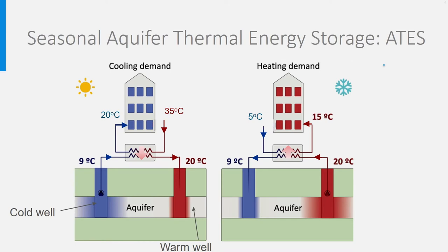In our example, we used a cold well at 9 degrees and a warm well at 20 degrees. Other temperatures could be chosen depending on the desired temperature levels. It is even possible to store high temperatures above 40 degrees.